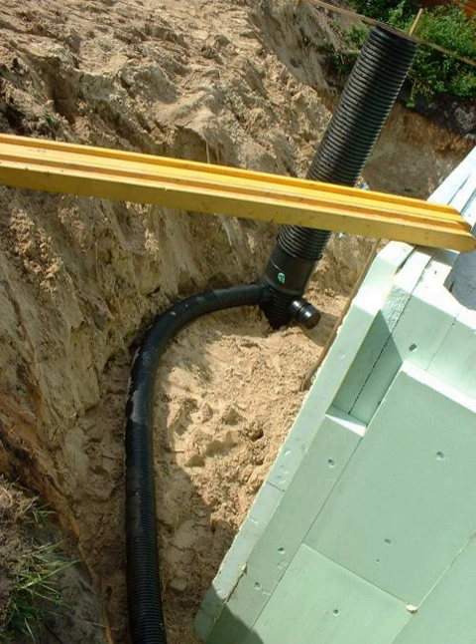When implementing in a house without a basement on a flat lot, an external condensation tower can be installed at a depth lower than where the tube enters into the house and at a point close to the wall entry. The condensation tower installation requires a condensate pump to remove the water from the tower. For installations in houses with basements, the pipes are graded so that the condensation drain located within the house is at the lowest point. In either installation, the tube must continually slope towards either the condensation tower or the condensation drain. The inner surface of the tube, including all joints, must be smooth to aid in the flow and removal of condensate. Corrugated or ribbed tubes and rough interior joints must not be used.